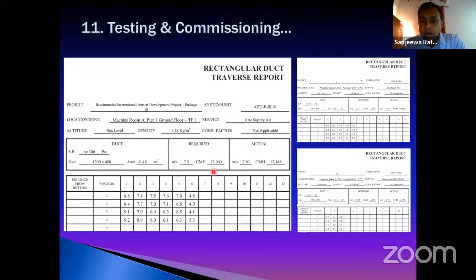Whereas the required rate, as per the design, is mentioned here. The required velocity is 7.5 meters per second, and the required flow rate is 12,960. So those are the readings, mentioned there. The other two diagrams are also for return air and fresh air. I'm not going to elaborate. You just think about this supply flow rate.